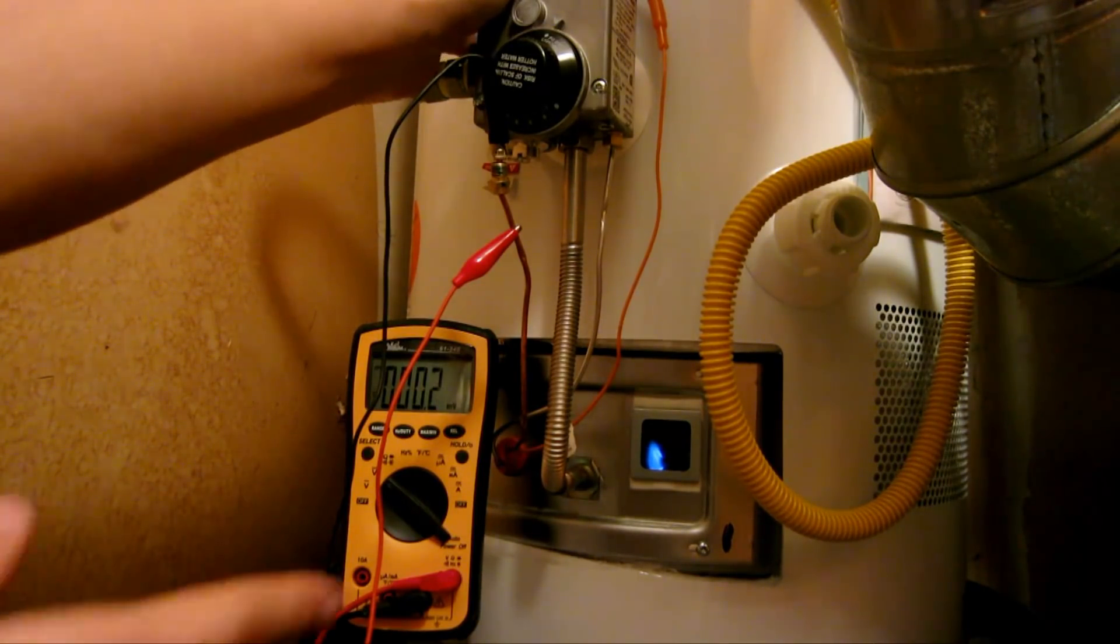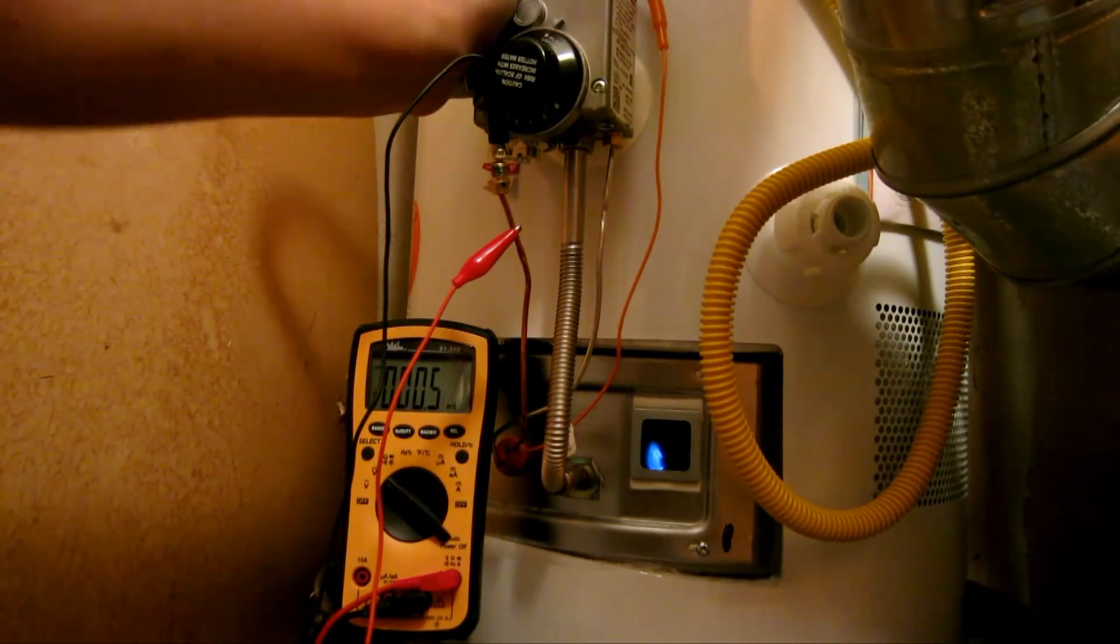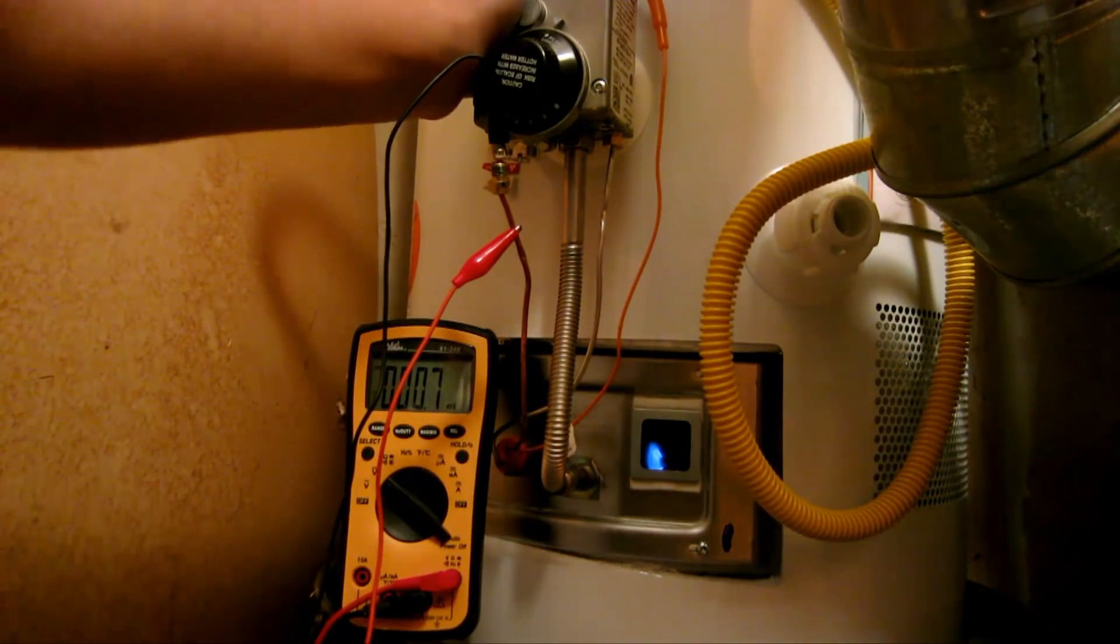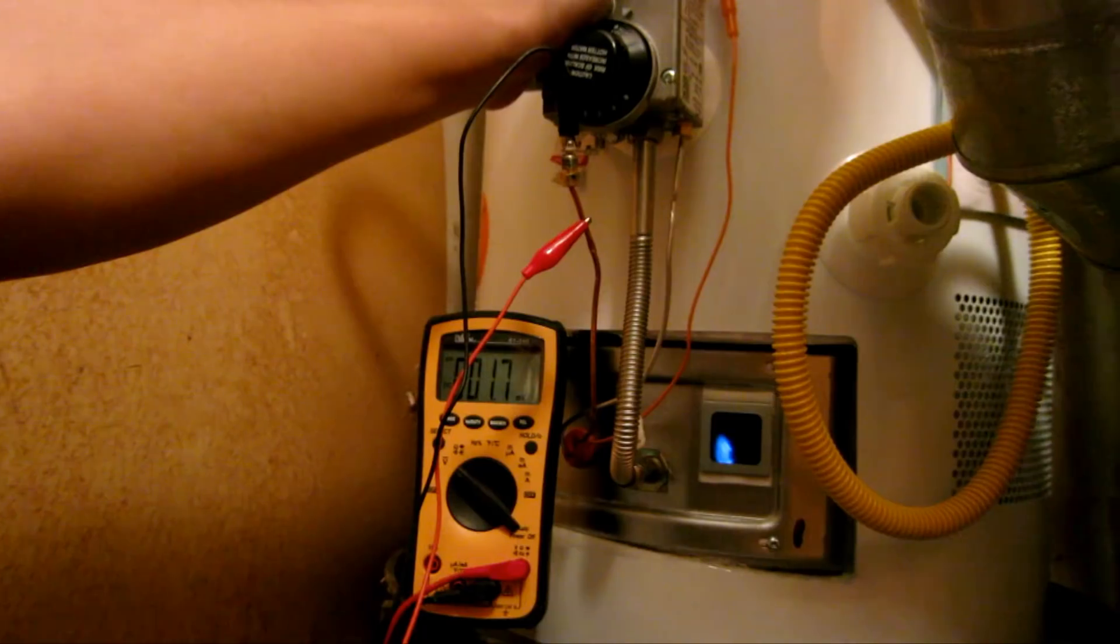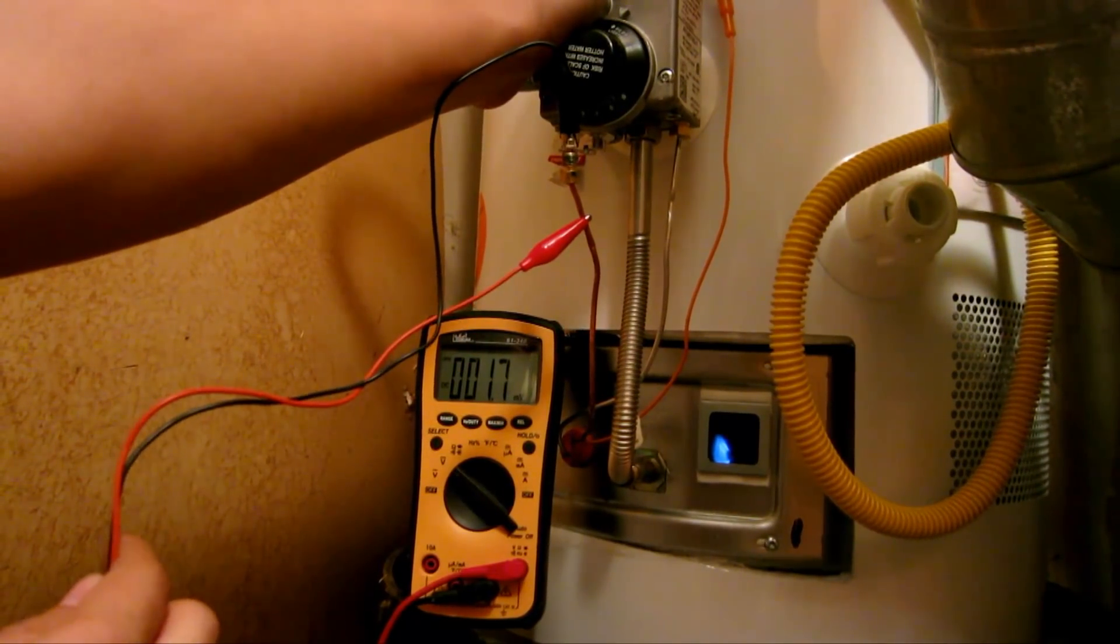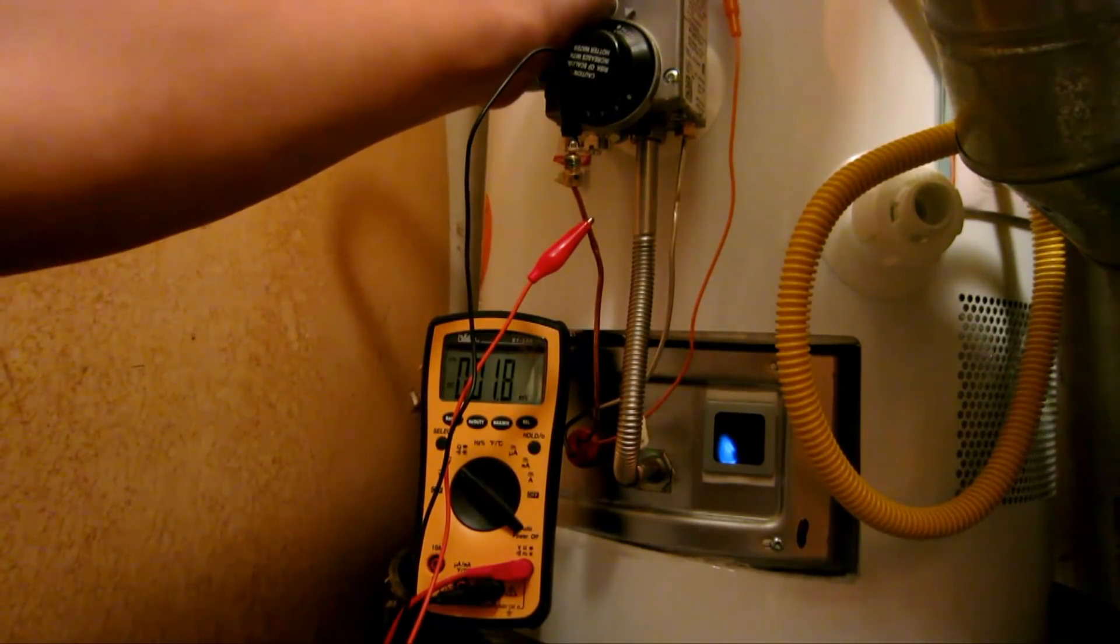Now, as a thermocoupler heats up, a slight voltage in the millivolt range starts to increase. And, I should get about 20 millivolts. So, it's been about a minute, and I only have 1.7 millivolts. That alone is a problem, because I need to have 20. So, I think I found the problem.